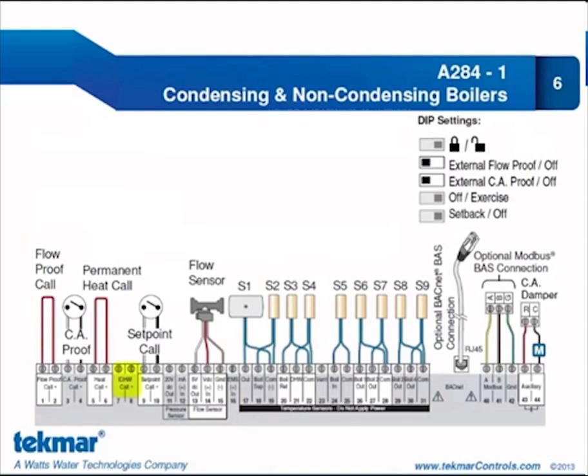You'll notice there is nothing connected to the indirect domestic hot water call terminals, even though we are doing indirect domestic hot water in this application. And the reason is because we are using a domestic hot water sensor instead. So the sensor is connected, meaning we don't need anything connected to the call terminals. If we were using an aquastat instead, of course the aquastat would be connected to those terminals.